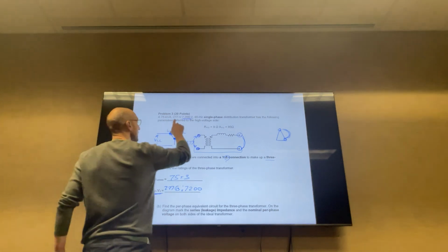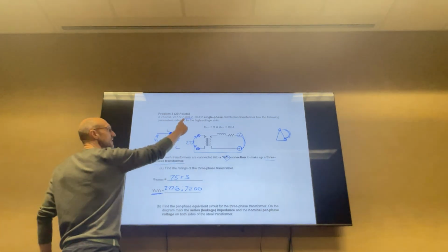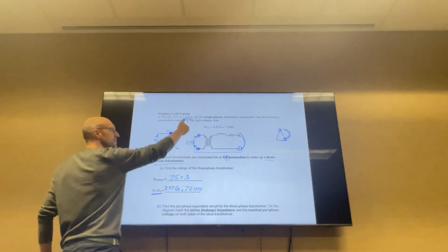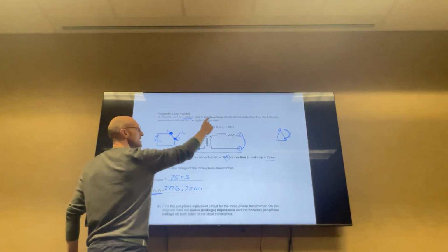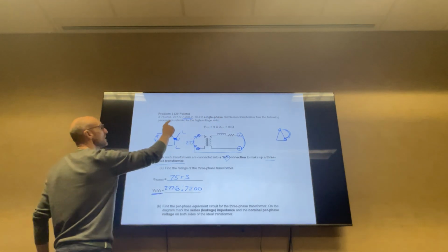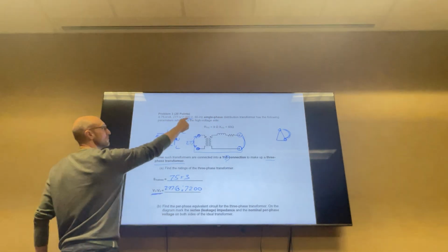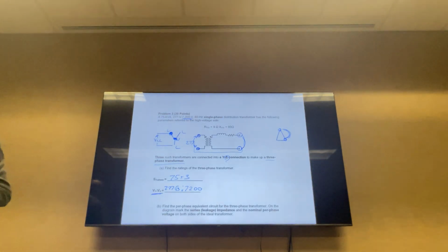Okay, so if this rating was given as a three-phase transformer, then they would both be line to line already. Yep. So if the problem said the 75 kVA, 277 to 7,200, 60 hertz, three-phase, blah, blah, blah, then this would be line to line and this would be line to line. And it doesn't matter their connections at that point. Yep. So it's only when it's in the single phase that we need to. Okay. Makes sense.